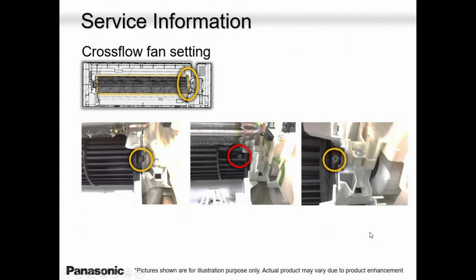Always, when you're doing your testing, when you're doing your repair, service call, always remember to check what's your return and your supply. Okay? 14 degrees Fahrenheit in 15 minutes time of operation, it's good. We are expecting 15 minutes, the fan to be running at a normal speed. That's why we want you to wait for at least 15 minutes. Also, for the compressor to be running at a very good frequency.